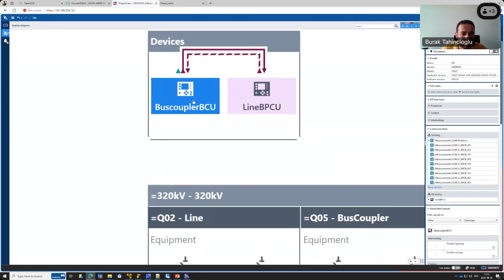Do you remember we had one GOOSE from the bus coupler to the line, where I can see the position information of the circuit breaker that is subscribed by the line bay controller protection. And the LineBPCU is also sending out one GOOSE, which is the trip information, and that would hopefully be subscribed by the bus coupler. This is our intention. Also, you see the GOOSE ID here, the GOOSE identifier, application ID, the communication parameters, the content and who is receiving. So it seems like we are on a good way of engineering. It seems that our engineering is what we wanted to have.